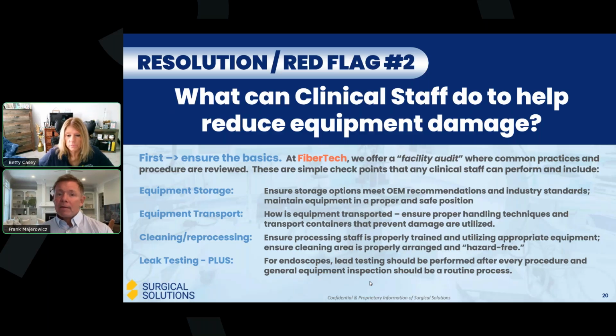Again, just make sure that everybody handling the equipment, including the cleaning room, understands the delicate components of it and is handling it safely and properly. And then a little plug here at the end for flexible scopes again: the good old leak testing. I'd be misrepresenting everybody if I didn't bring up leak testing. One of the most important things you've heard before with a flexible endoscope is leak testing. It's the difference between catching a leak and not catching it and continuing to use the instrument, leading to a $5,000 repair or more, which could have been a $500 repair if you simply would have caught the leak. So probably one of the biggest budget busters, I call it.